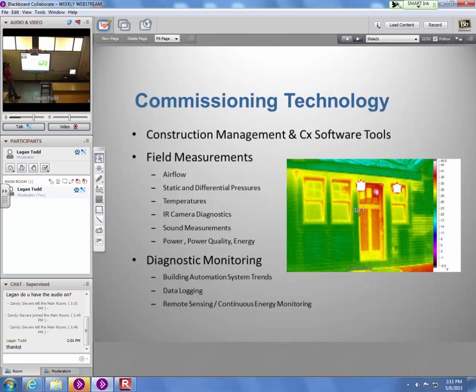Diagnostic monitoring is what we do, either with data loggers we've deployed or using the building automation system and its trending functions to watch parameters associated with system operation over time, and to further verify things. Sometimes when you do a functional test, you're there with a given system for an hour to a couple days, but you're still just seeing a snapshot, watching operation within a short duration while trying to simulate varying conditions.